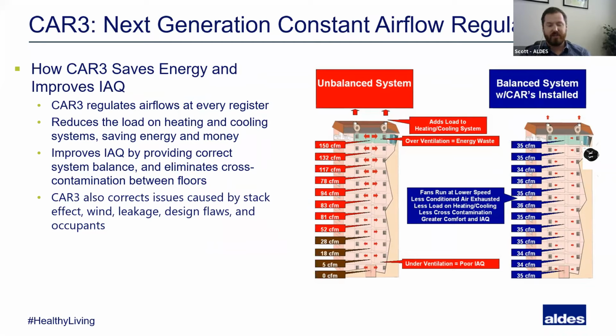What we have shown on this slide here is a pretty typical kind of application. Up near the fan, you have more pressure. Typically, you're going to have more flow. Down at the bottom, less pressure, less flow. We've done a lot of case studies where we've done before and after measurements, and this is pretty consistent with what we see, unless you've got a stack effect issue, and then you're actually going to have a lot of airflow at the bottom of the building. But this is pretty common for day-to-day, and obviously I'm over-ventilating at the top and under-ventilating at the bottom. My over-ventilation at the top doesn't do anything for my air quality other than cost a lot of money. And at the bottom of the building, people don't have good indoor air quality.